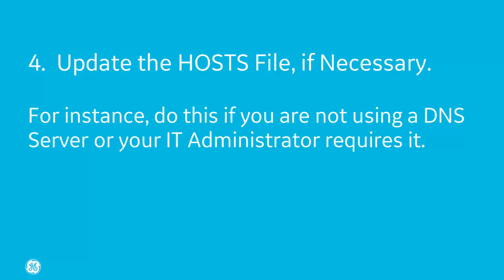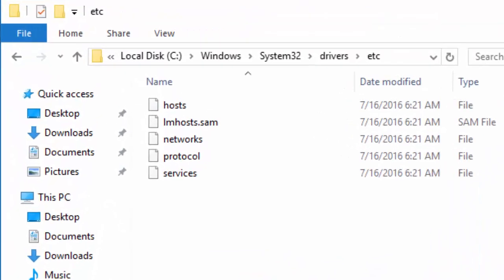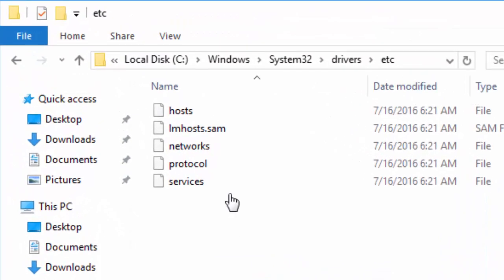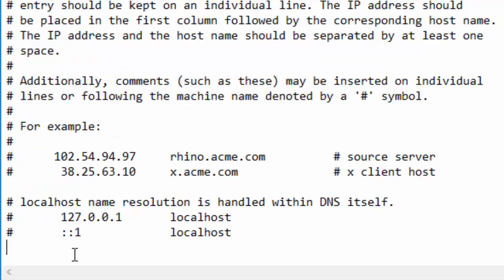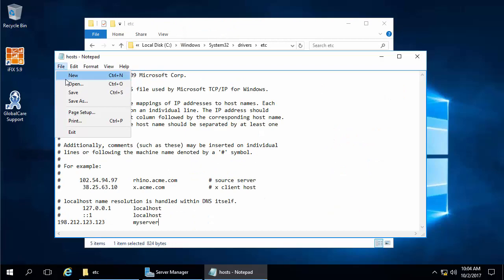For your fourth and final step, if iFix is not on a domain you probably need to update the Windows host file. This isn't a step that everybody has to do — it depends on your setup. This file assists Windows in resolving host names with their IP addresses. From Windows Explorer, find the host file in the Windows\System32\drivers\etc folder. Edit this file in a text editor like Notepad. Add the IP address and the computer name, then save the file.